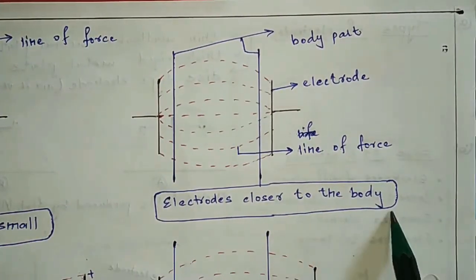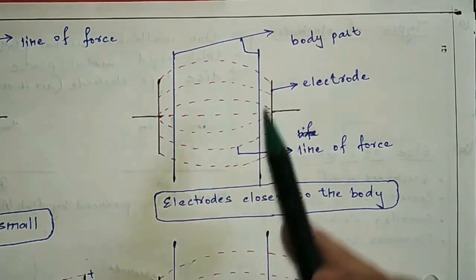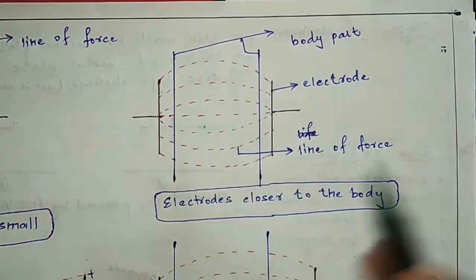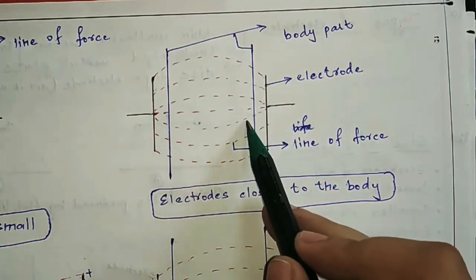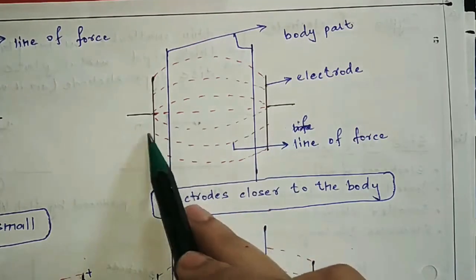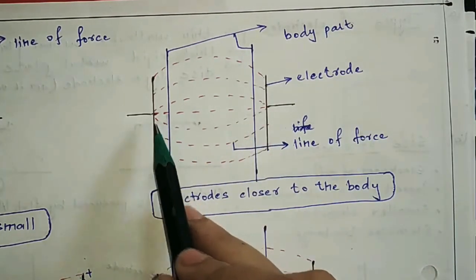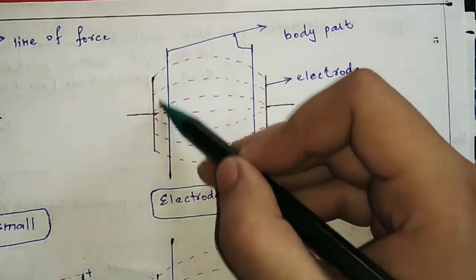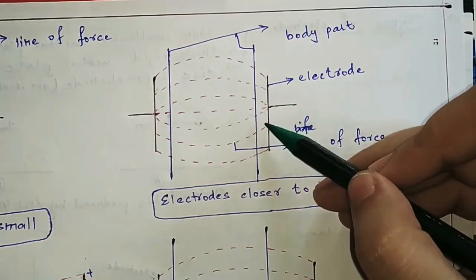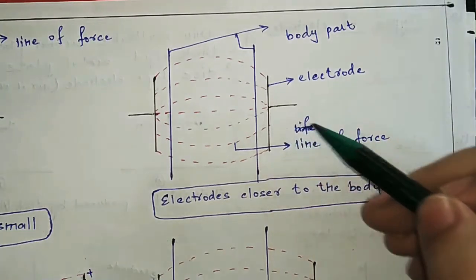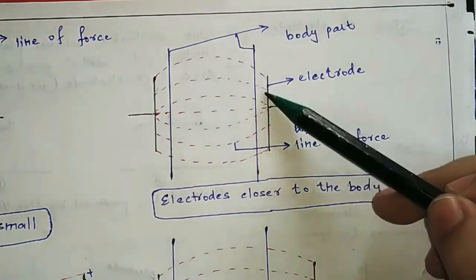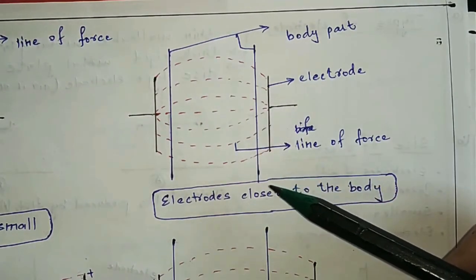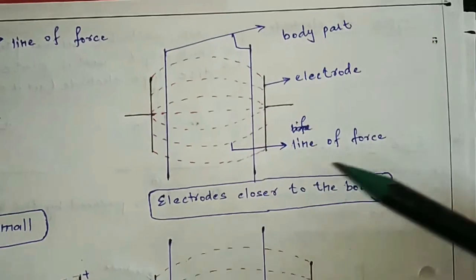If the electrode is too close to the body, the concentration of the electric field will be more at the superficial level, resulting in superficial heating rather than the required deep heating. Similarly, if the electrode is at an uneven distance, the concentration of the electric field will be uneven — more on one side, less on the other — causing uneven heating.